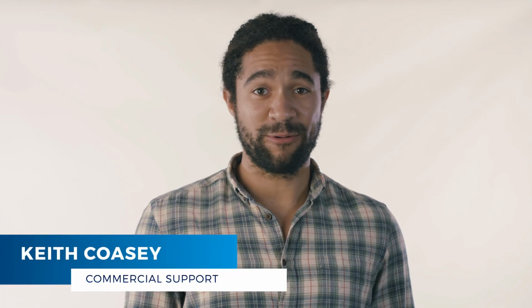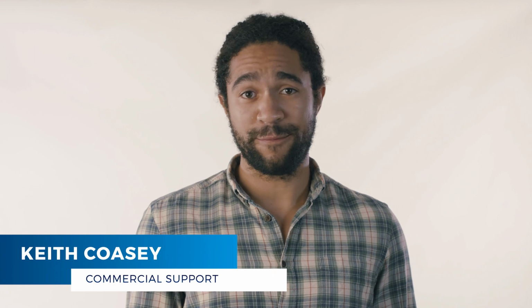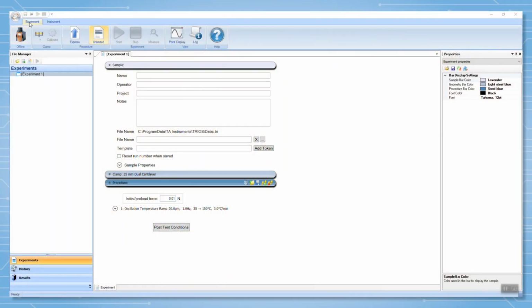In this tech tip, I would like to show you how to access the help menu functionality for the DMA 850. In the TRIOS software, all of the relevant documents for the dynamic mechanical analyzer can be found under the experiment tab, where there's a help button icon.